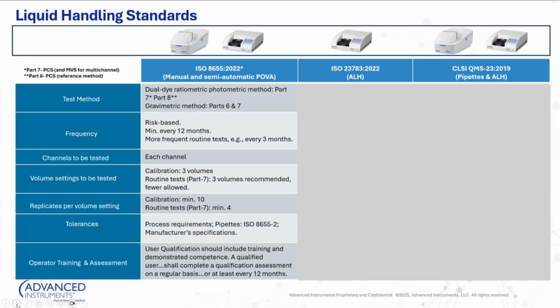Now, when we think about replicates per volume setting, a full calibration means 10 replicates at each volume. So if you're calibrating an adjustable volume pipette at 3 volumes, 10 times 3 is 30. That means 30 replicates to perform a calibration according to 8655. For routine tests, you can have a minimum of 4 replicates. So again, routine tests are meant to just be that quick check. Make sure and answer the question of, is this device still within its calibration? Maybe somebody dropped the pipette and you just want to check it quickly, or maybe something got aspirated into the body of the pipette and you want to make sure that it hasn't been contaminated, make sure that it still is A-OK.